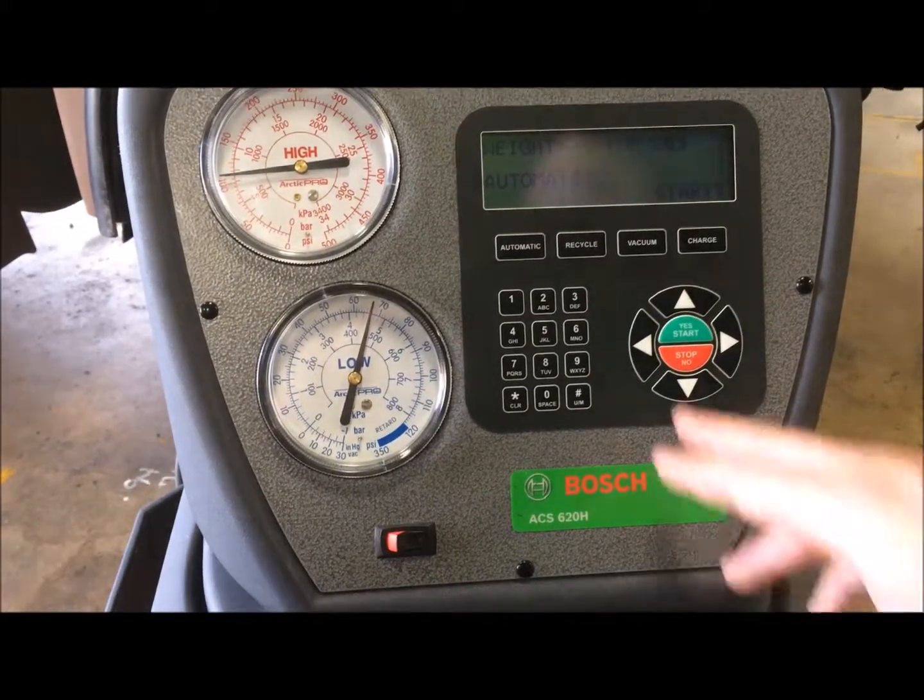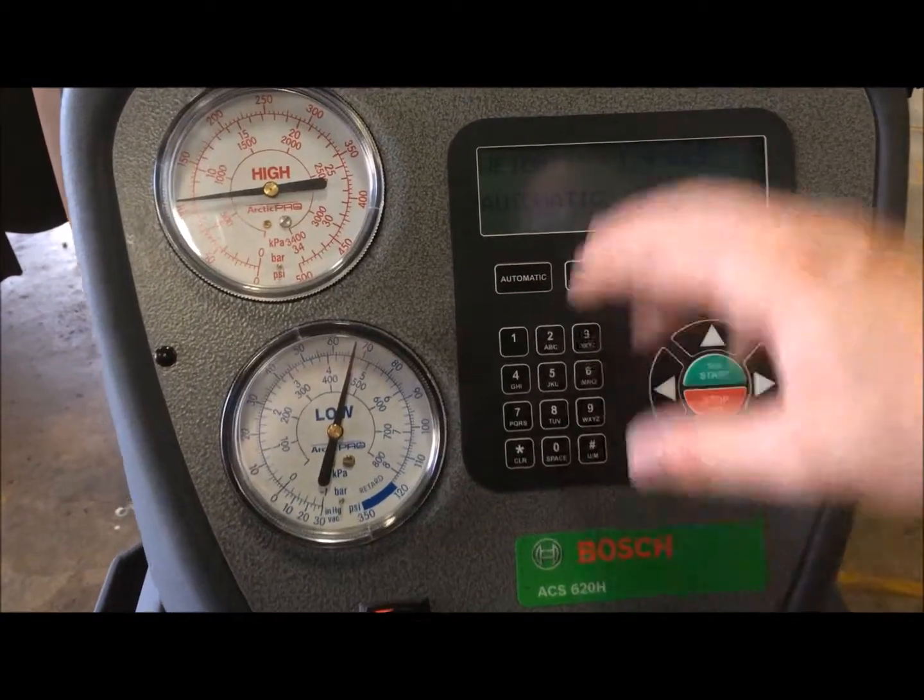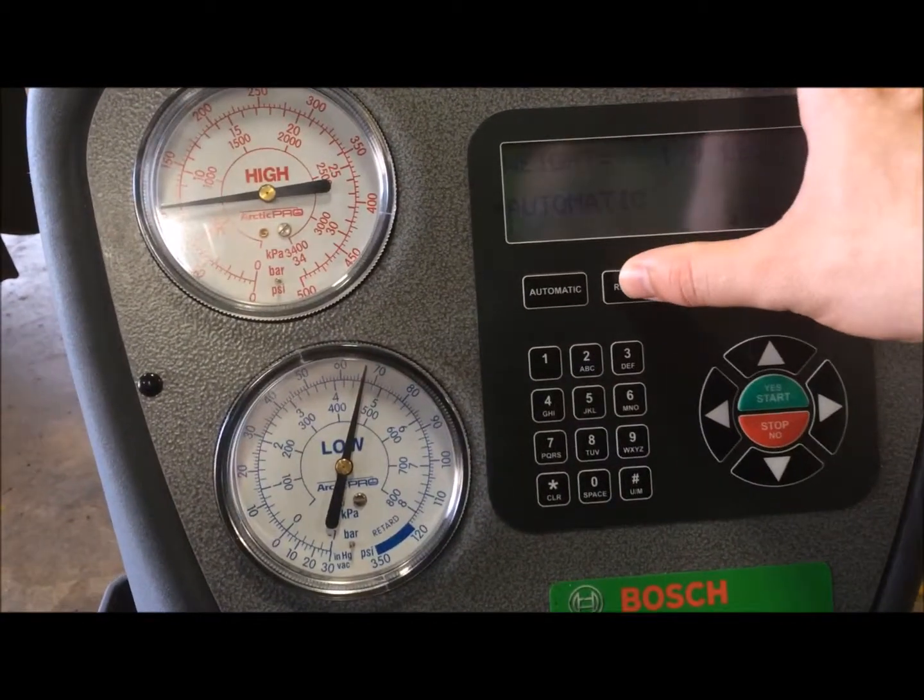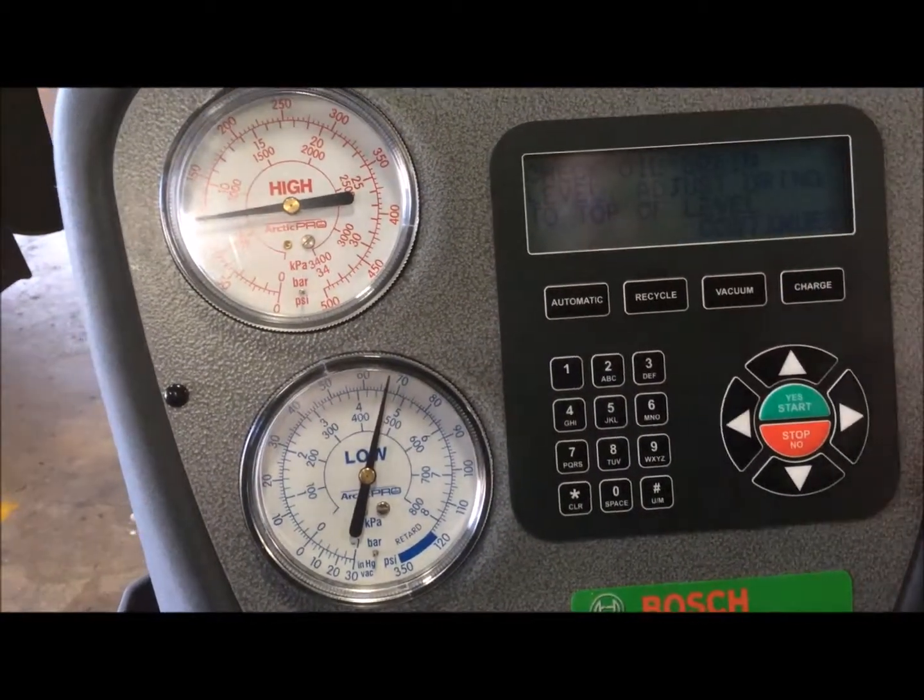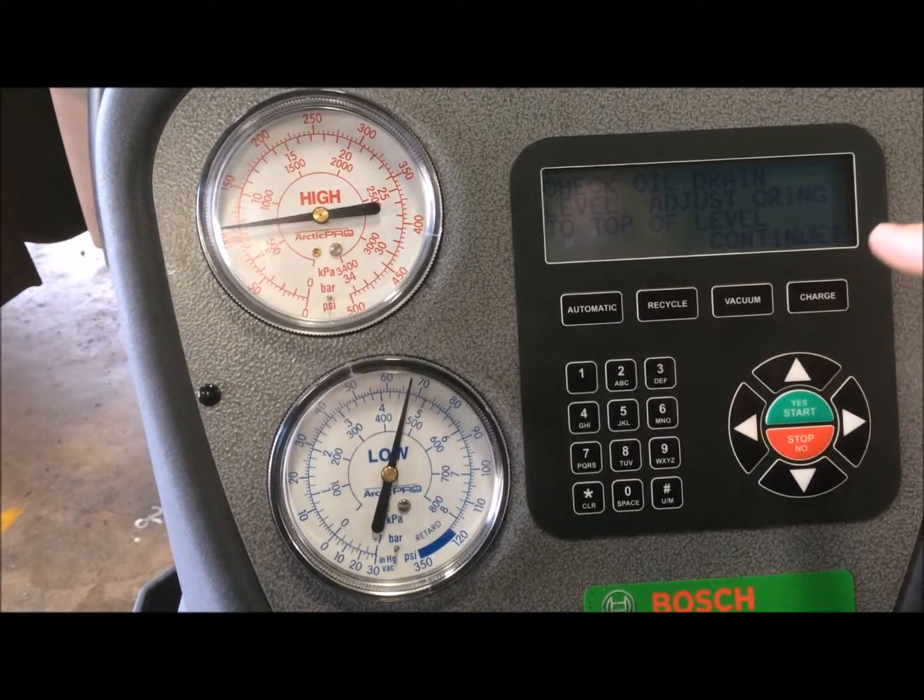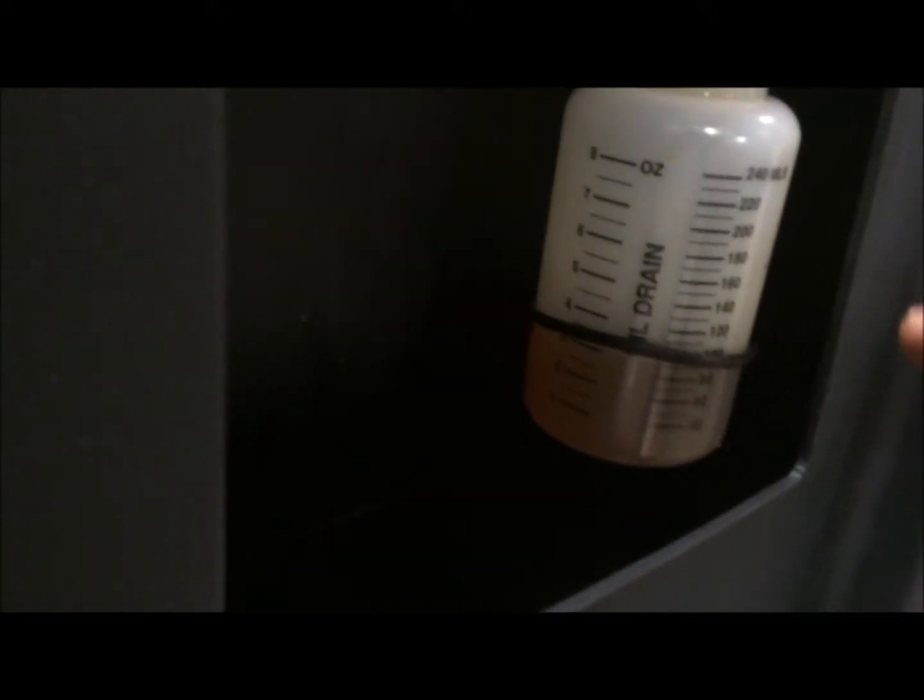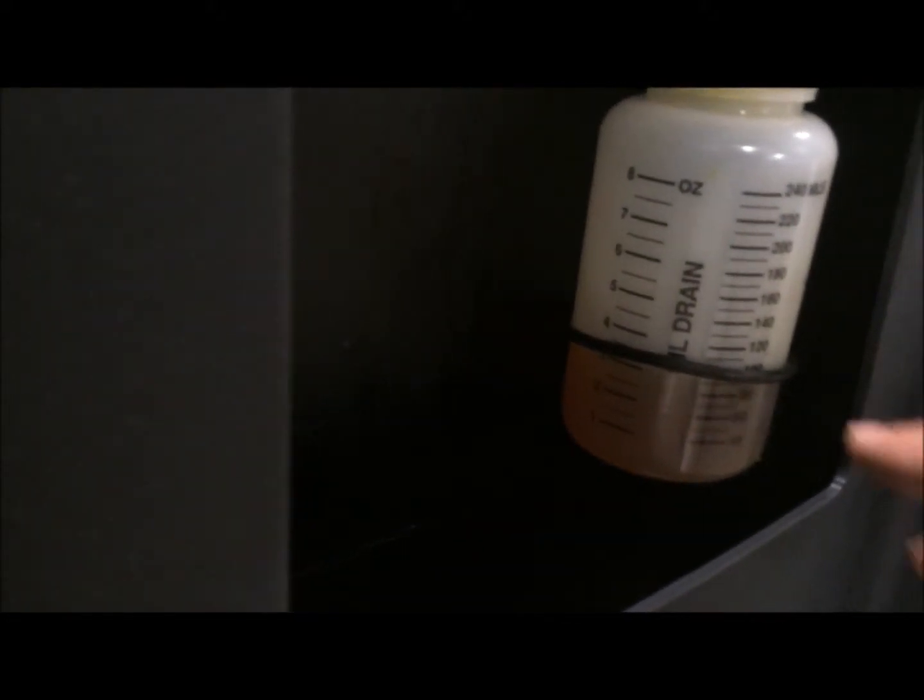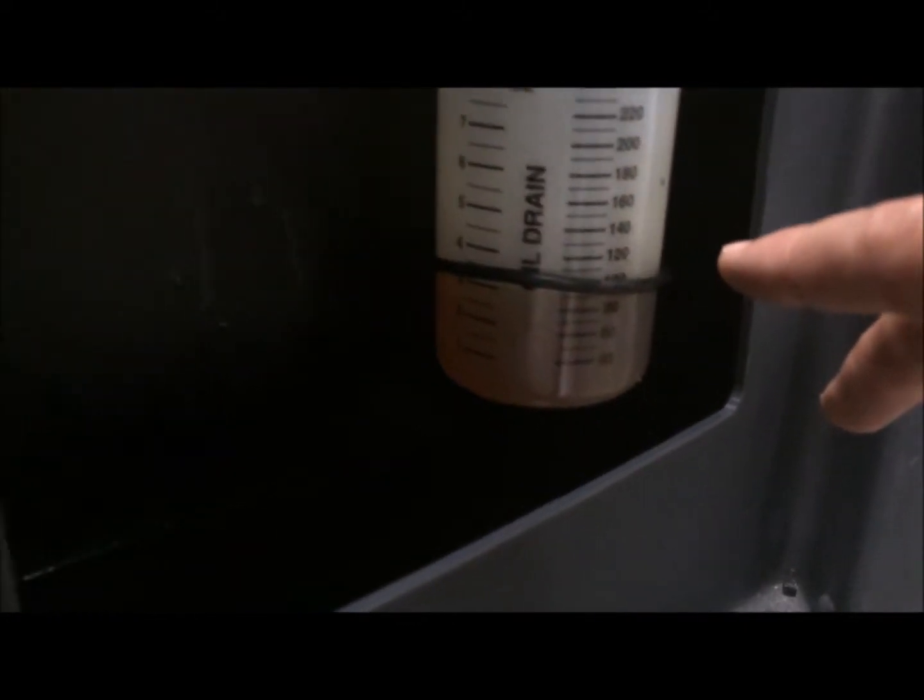Alright, first thing we're going to do is hit the recycle or recovery button. It's going to ask you to check the oil drain, the level right here. Whatever oil on top is the oil that you're going to recover from the system. So we marked it as right about 100 mil, right here.